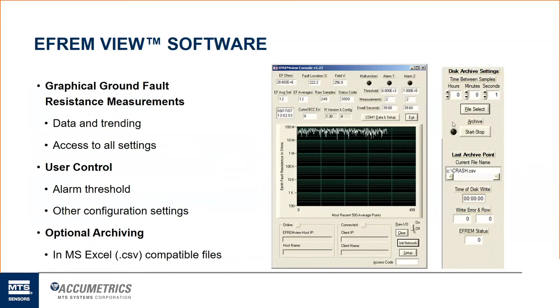On the right hand side, you can see the disk archiving setup that allows the user to start archiving the data, and it will export that to a Microsoft Excel .csv file, and they can look at that data over a much longer period of time. Again, we would probably suggest they do that once that initial ground fault alarm, that warning alarm, comes in. They don't need to do that all the time. That's what they're utilizing, that 4-to-20 current loop output. That's the trending feature that they're most concerned with monitoring.